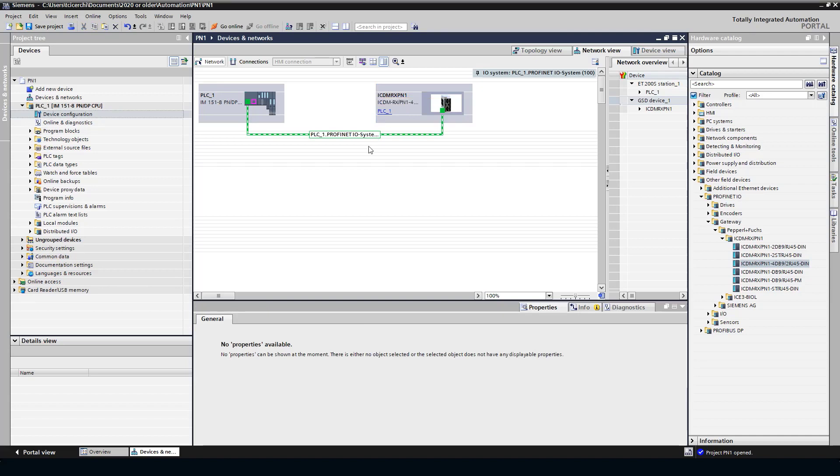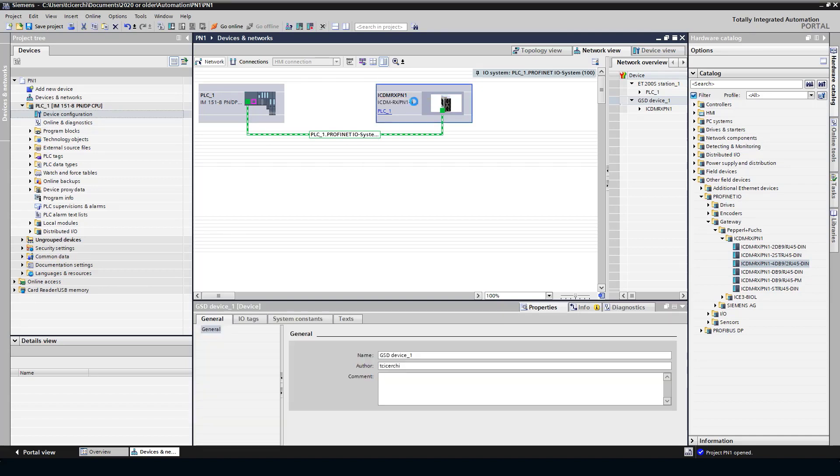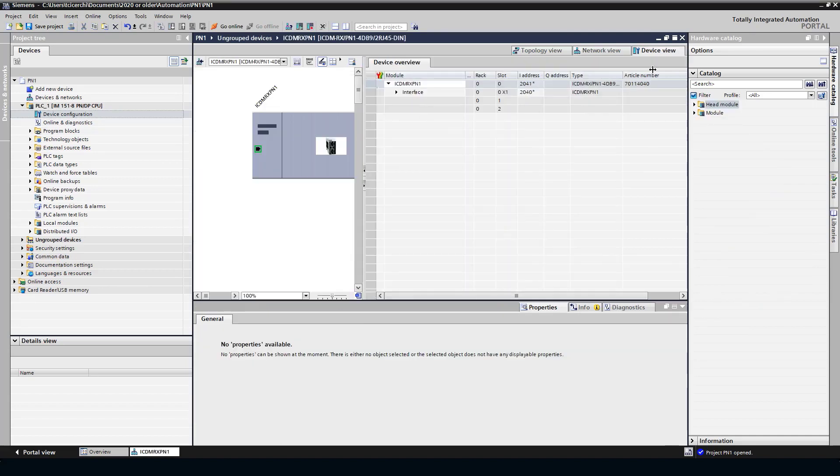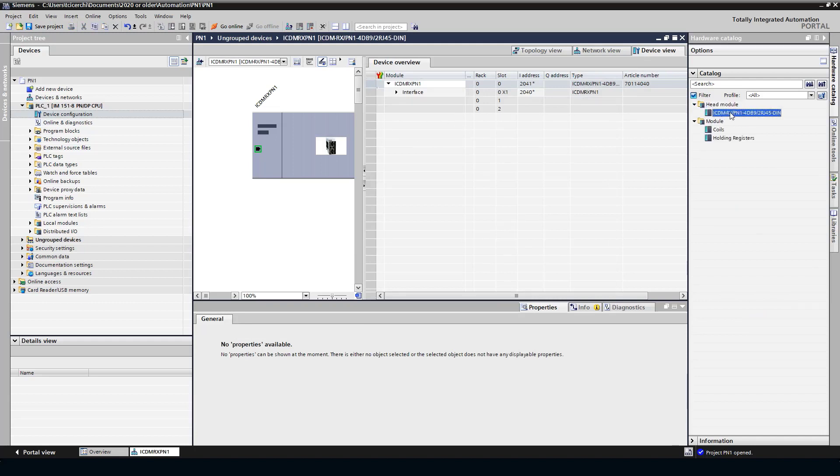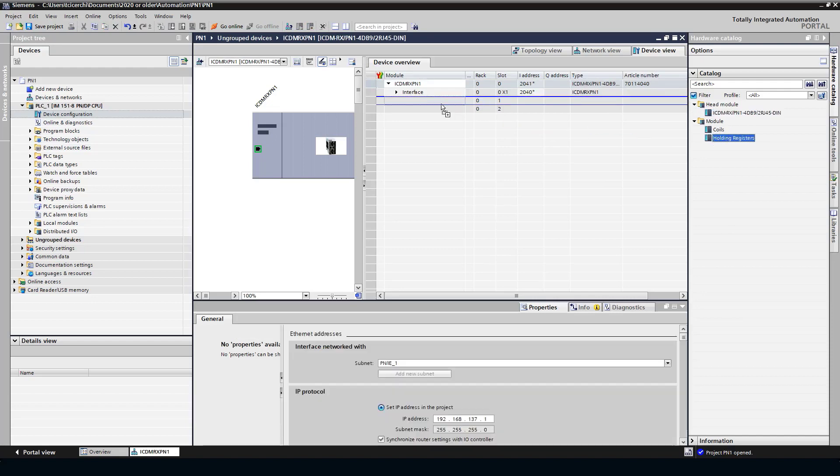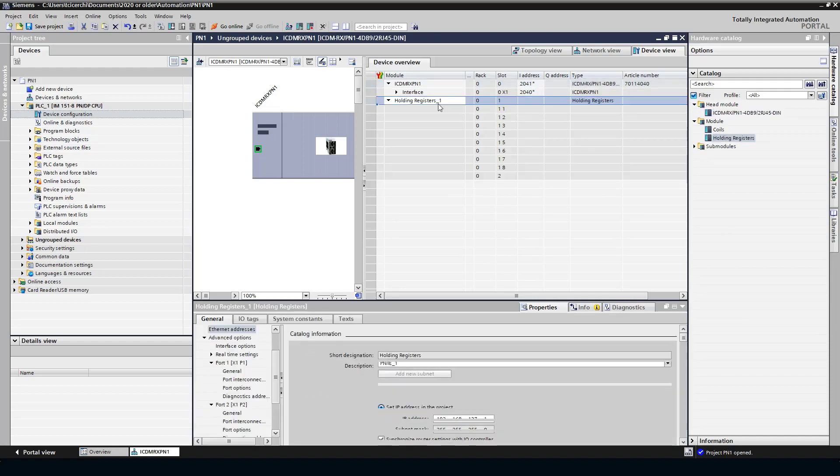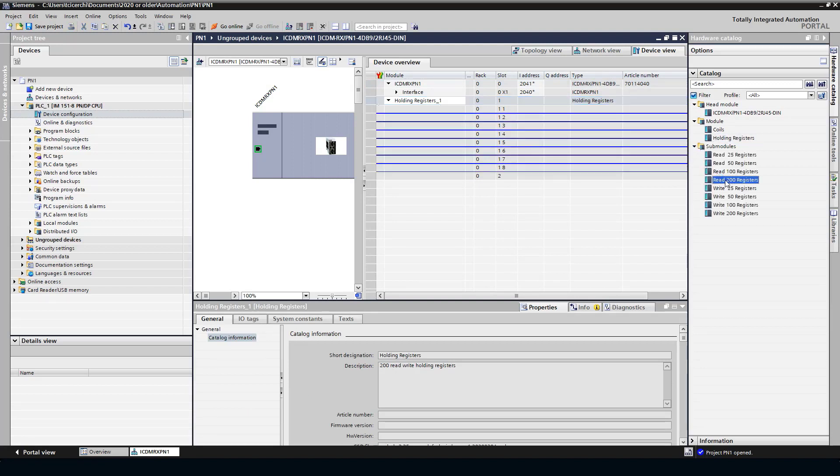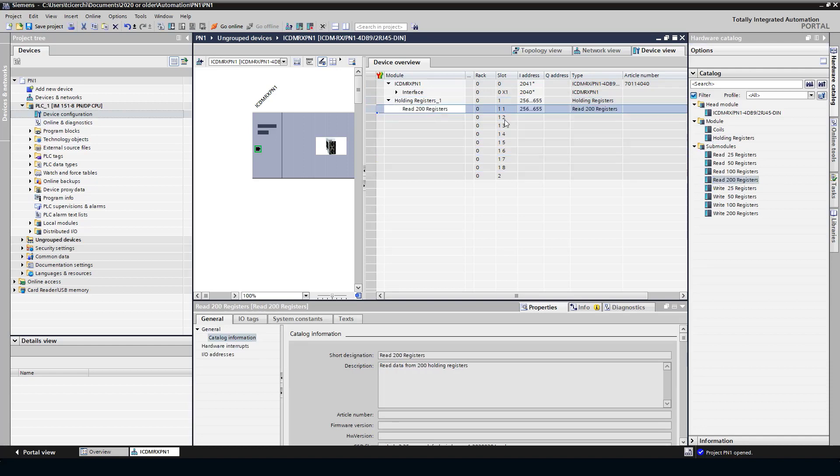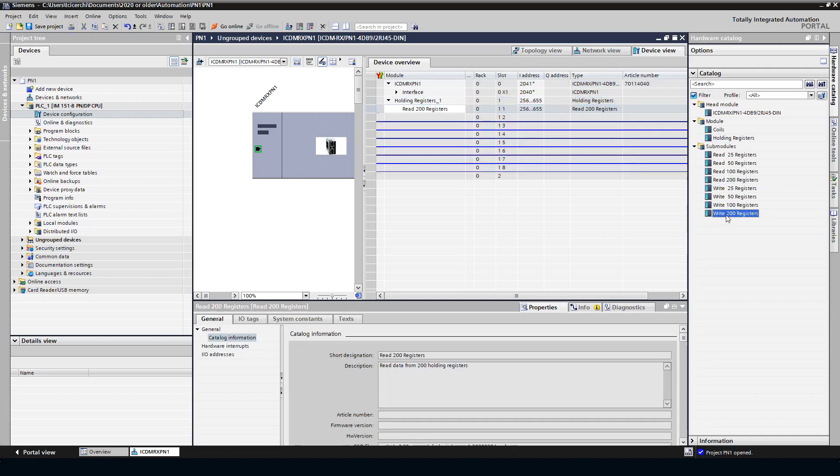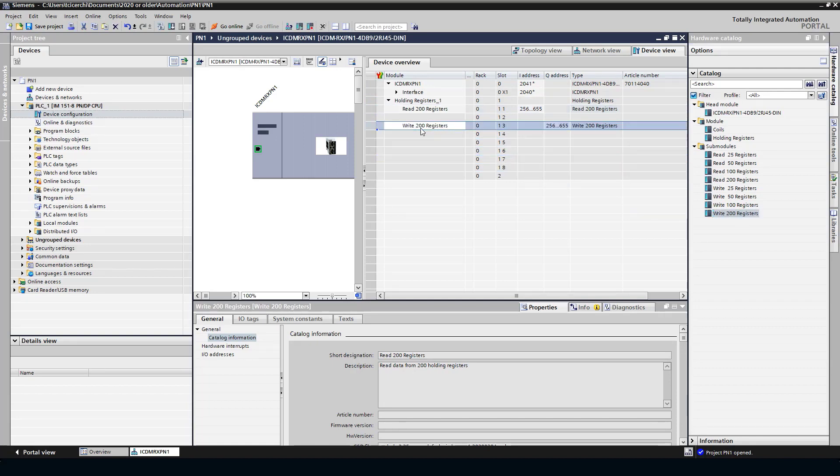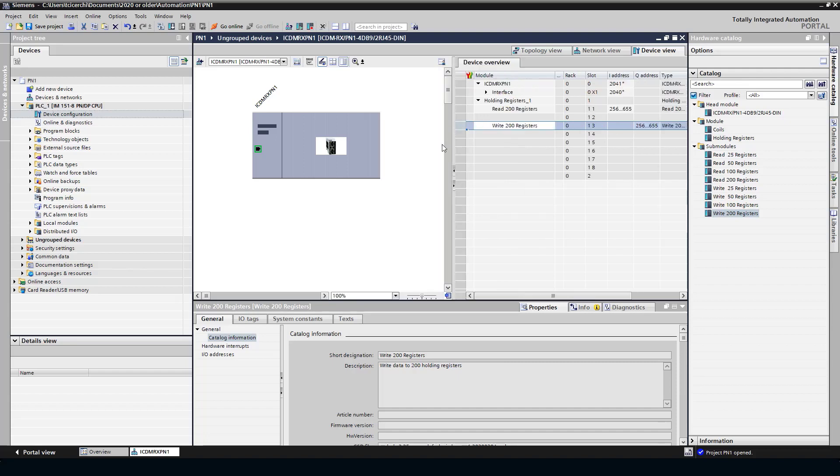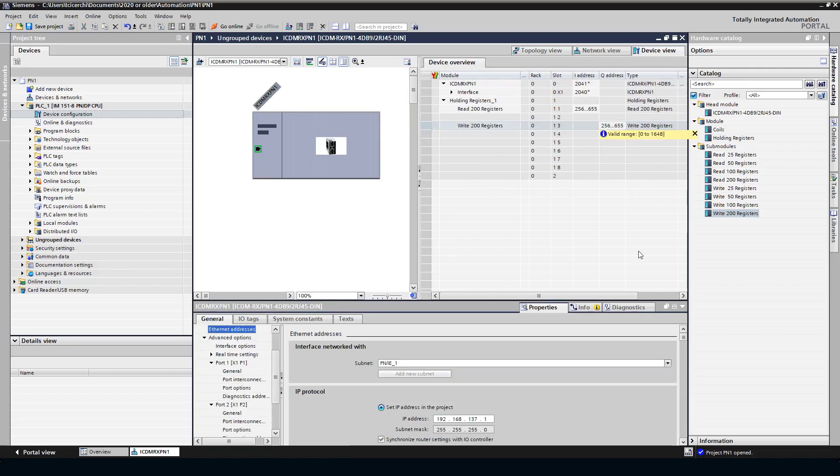Now, once I've done this, I'll usually double click on it. It pulls up the device view. What I want to do here is, number one, I just said I'm doing only a holding register. So, I'll drag holding registers over here. And then, I want to fill up my sub-modules. So, my two sub-modules are my read 200 registers right there and write 200 registers. It's way more than I need, but that's okay. Just make sure you fill it in correctly, slot one and slot three.